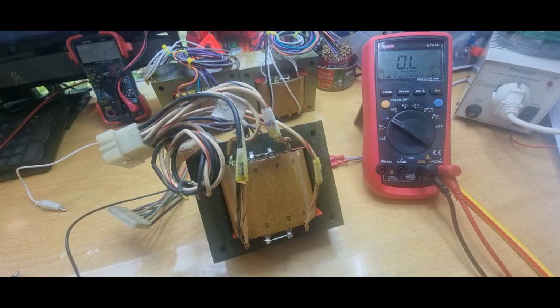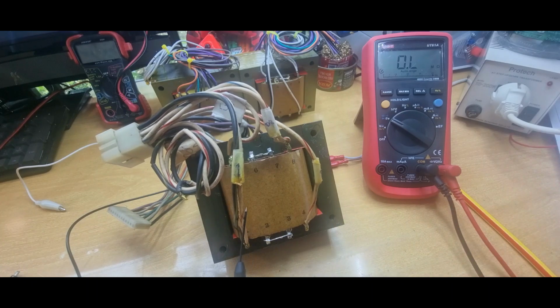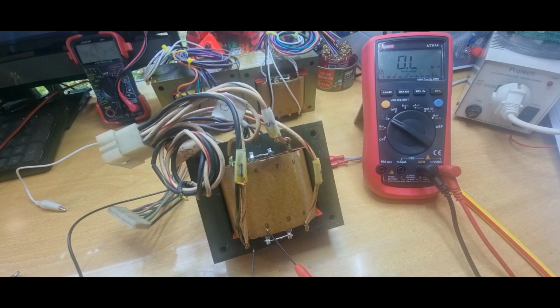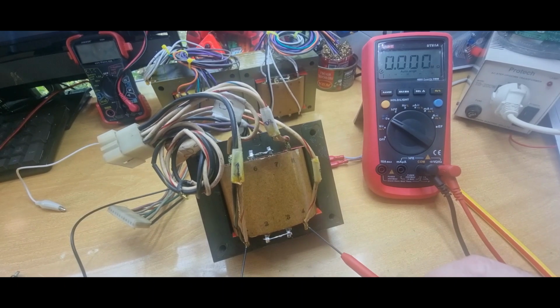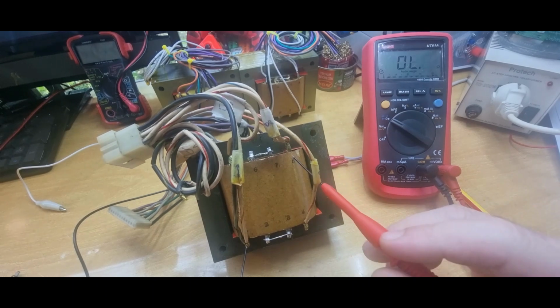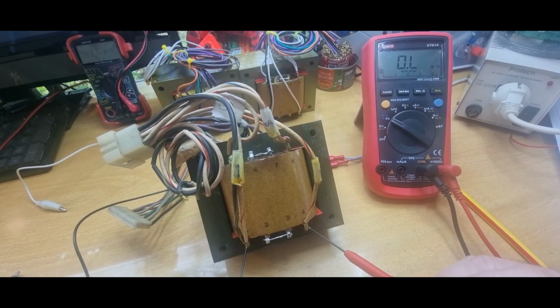I'll cover how you can test whether the windings are opened or shorted. Between a winding, you're looking for very low resistance — the lower the better. Low resistance indicates no open, and if you do the math deeper, it also indicates the size of the conductor, the size of the windings inside.